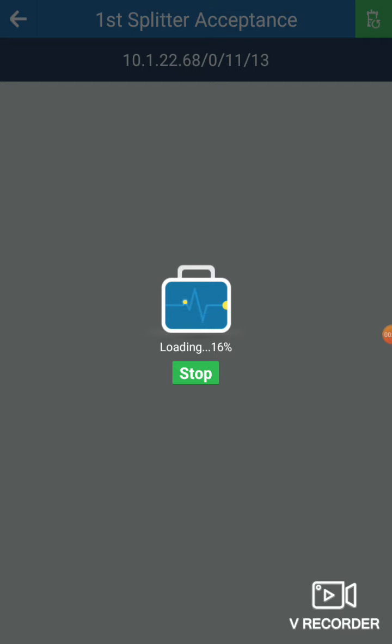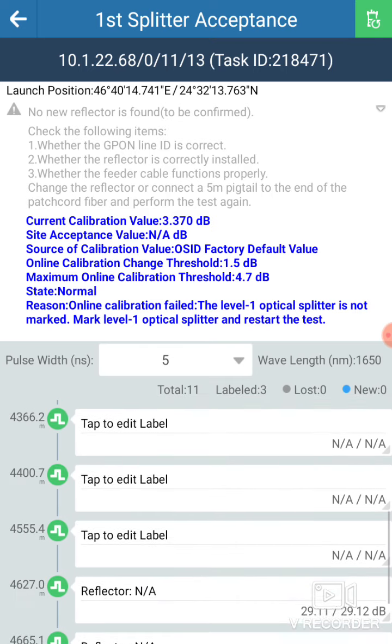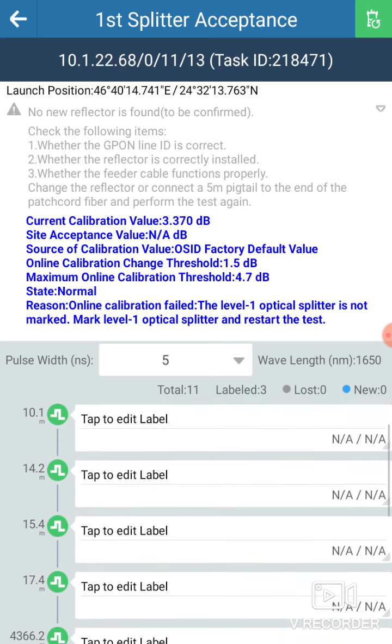So the issue here is from the optical mark level 1 splitter. We need to do this first in the first splitter. After loading, I will teach you how to do the labeling and type. You see there are a lot of big numbers coming. This is the issue — the reason online calibration failed is the level 1 optical splitter is not marked. So let's start the test.